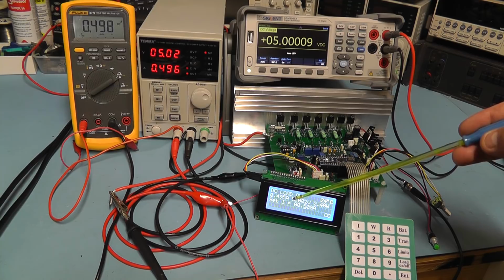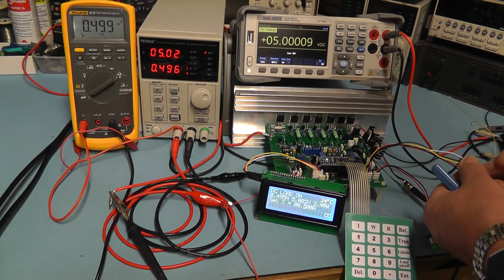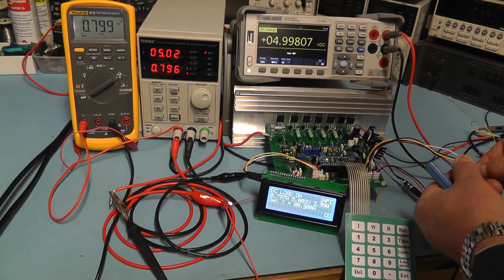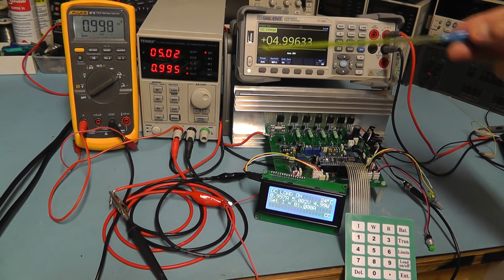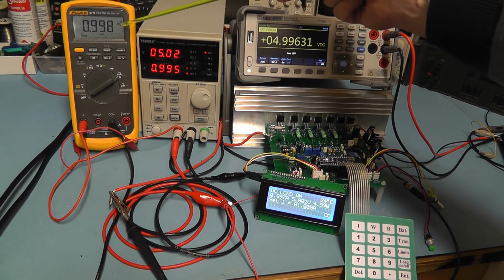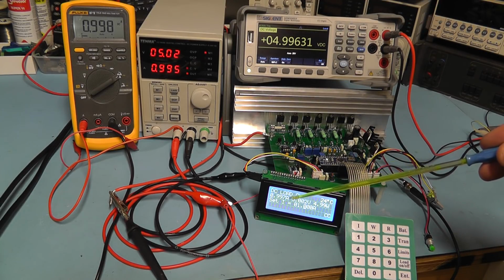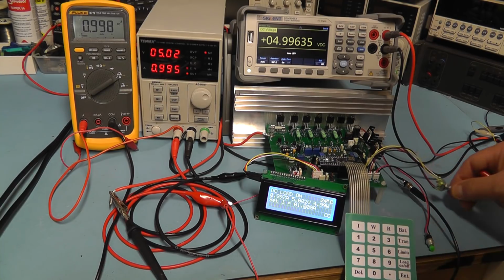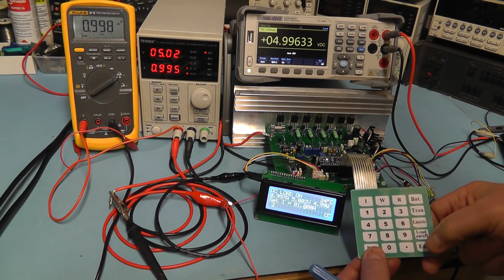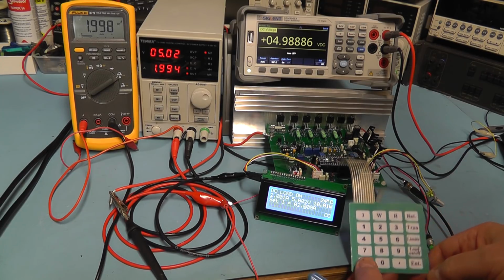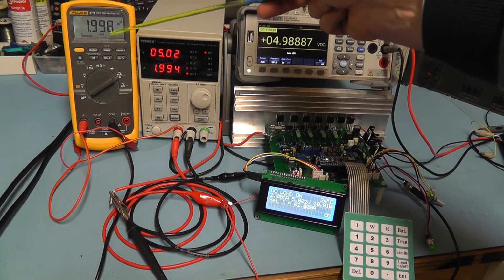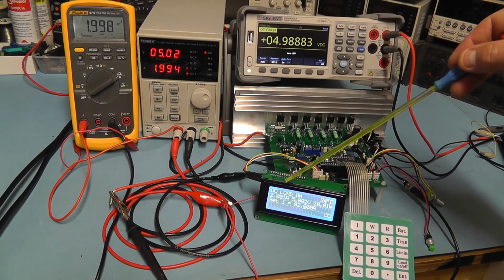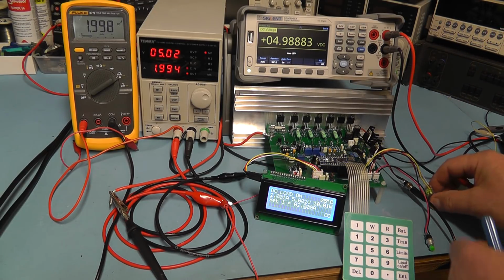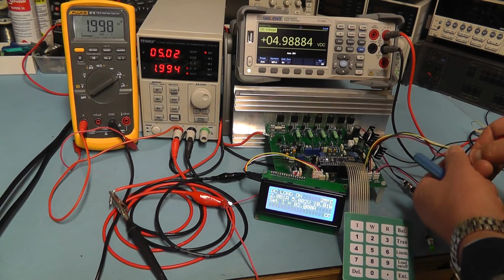Here we've got on the DC load 495. Let me go up now to 1 amp, and the Fluke is showing us 0.998. It was hovering there between 0.998 and 0.999. That's close enough, as we have there on the DC load. Let's now go up to 2 amps. It's showing us 1.998 amp on the Fluke, and it's showing us 2.001 on the DC load. So let's go up to 3 amps.